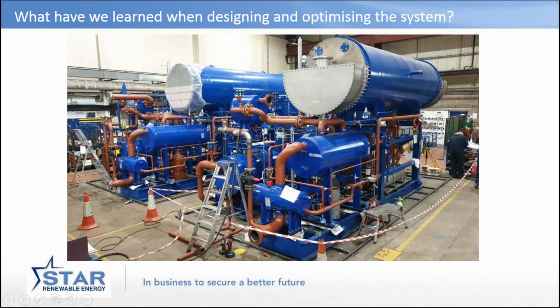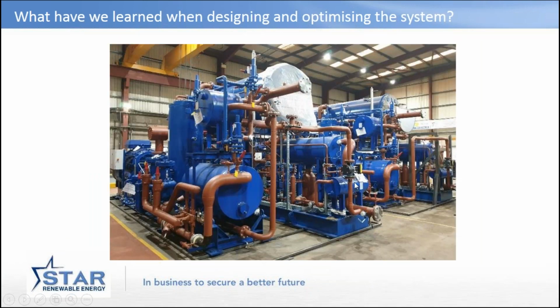The interesting bit, and this is really the main part of today, is the warm end of the heat pump and how we improve the efficiency of this. Why do we go to so much bother to make this look so complicated? Because a simplistic diagram has an evaporator, a condenser, a compressor, and an expansion valve. There are only four components in the heat pump, and yet this looks much more complicated than that. The reason we're doing this is to try and get extra performance.